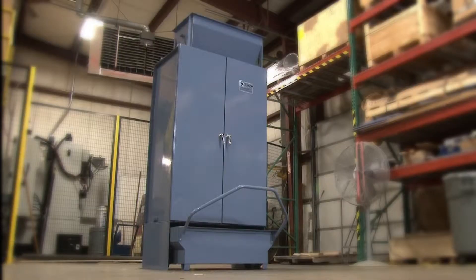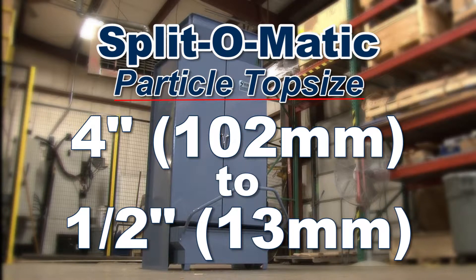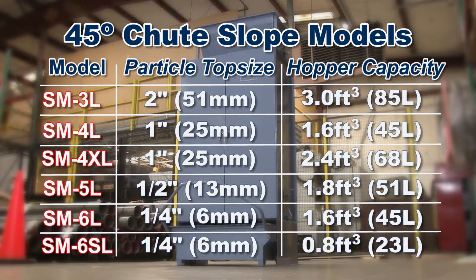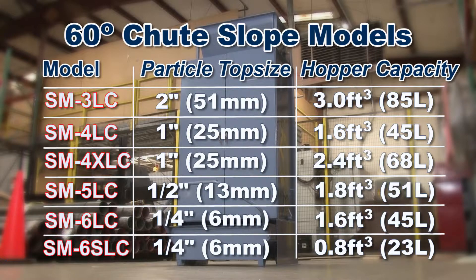With a recommended particle top size range from four inches to one-half inches, Gilson offers multiple Split-O-Matic splitter models to choose from. Standard models are designed with 45-degree chute slopes, but Gilson also offers models with 60-degree chute slopes, which are designed for low-specific gravity materials such as coal or coke, and materials with a large fraction of fines.